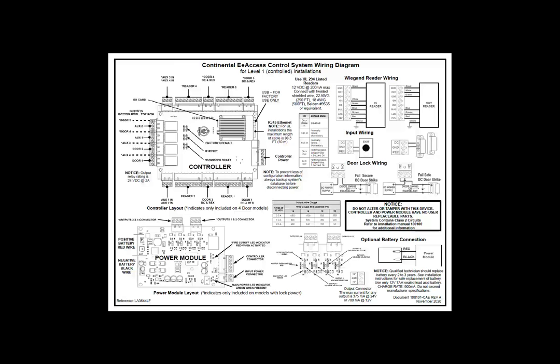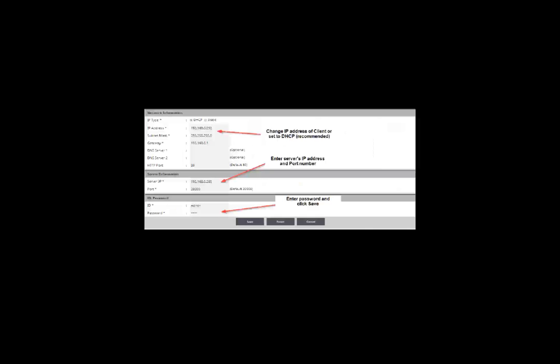All eAccess controllers can be configured as either a server or a client to expand the amount of doors in the system. eAccess system supports from 1 to 128 doors and up to 64 panels or controllers. All systems require one server. In addition to the server, you configure additional controllers as clients or elevators to increase the number of doors or elevators. The options enabled in the eAccess license key determines how many clients are supported and also which features are enabled in the system. When configuring a client, you must specify the IP address of the server. The clients point to the one server.